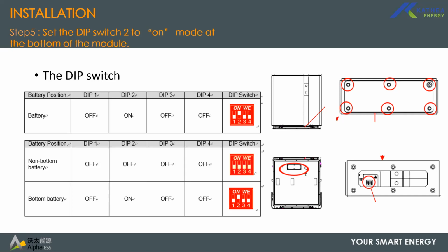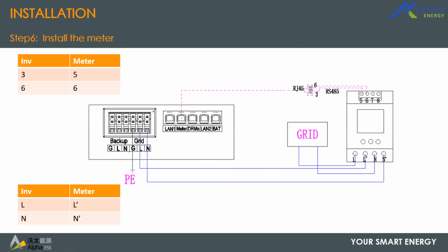So to access that, you would need to open the battery cover. You just pull it back, and there is a small plate with 2 screws. If you open that plate, inside you would see DIP switches there. Then you just set DIP switch number 2 to on. So that basically gives the inverter an end of termination for the battery such that it can know how many batteries are connected to the system.